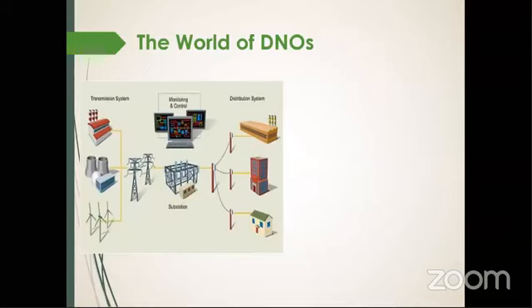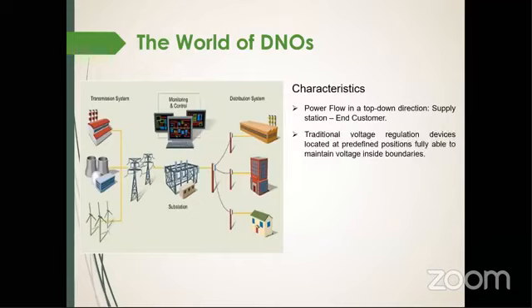Let's start with how distribution networks used to look and operate for decades. Distribution grids were completely passive networks with the sole aim of transferring energy from supply substations, i.e. from transmission networks, to end customers. There were no active power resources located in the distribution grid layer, so power flow was in a top-down direction from supply substation to end customer. Traditional voltage regulation devices were located at predefined positions preset by operators and were fully able to maintain voltages within boundaries without almost any interaction by the operators.